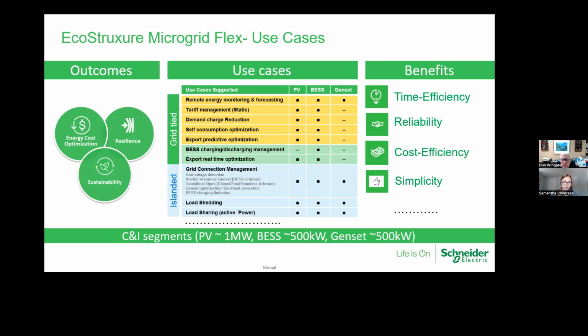Increasingly, we're seeing a need from the utility perspective to minimize export. So if your utility interconnect agreement says no export of your battery storage or generator, one of our standard grid-tied use cases is real-time export management—so you don't have to export, or you can export just your minimum requirement from the utility. Those things are configurable.